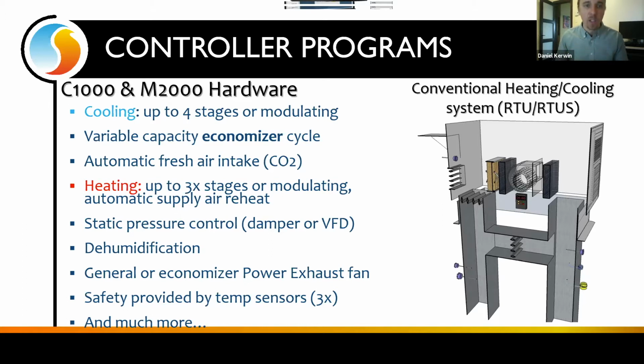When looking at the cooling side, we can do up to 4 stages of cooling. However, usually with the light commercial units, we only need 2 stages of cooling. We can also do modulated cooling. So if perhaps it's not a packaged rooftop unit, but more of an air handler in a mechanical room with a chilled water valve, we can control a modulating chilled water valve. We can control the economizer for fresh air, and we also have a dedicated input for CO2 levels. So if we want to do demand controlled ventilation, or DCV, we already have that embedded within the controller. On the heating side, it can be staged heating or modulated heating.